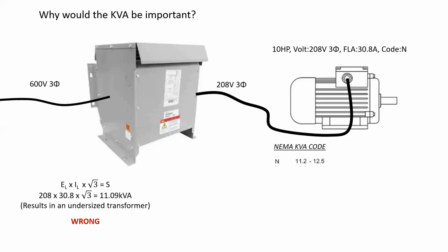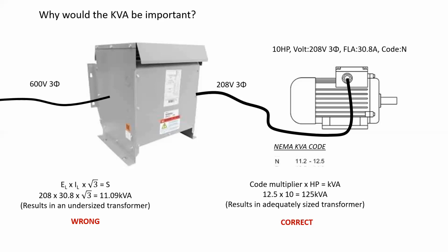Instead, what we do is look at the NEMA KVA code. For N, that's 11.2 to 12.5. I take the horsepower and multiply it by the code provided, which gives me the minimum KVA that I would require in order to supply this motor for its starting as well as its running. And you can see it's a substantial difference in size. The minimum size transformer is 125 kVA.